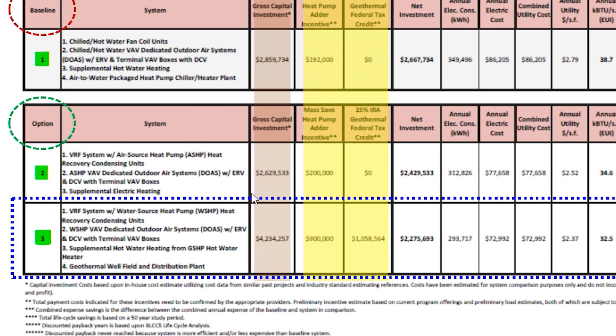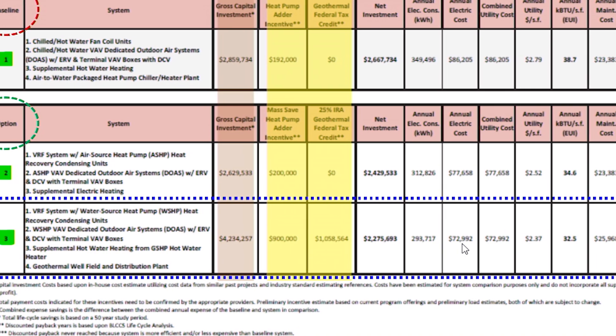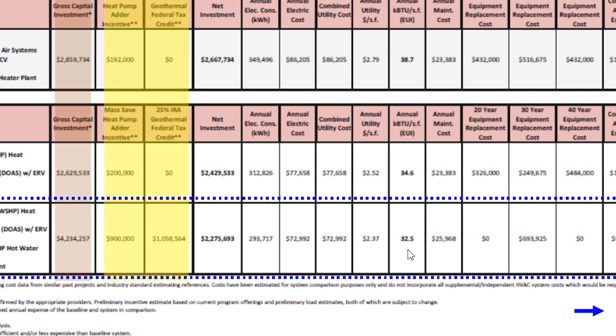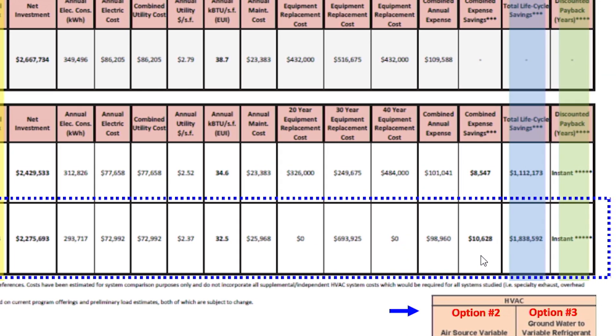The third option — the geothermal — is the one the committee chose. On paper it shows that it's 1.4 million more than the base system; however, you get a significant amount of money through both rebate programs, so your net investment is right around 2.2 million. Energy costs are comparable, electrical costs comparable, and we do save some money in equipment replacement and maintenance. In the long term, lifecycle savings over the base system would be just over 1.8 million — more than option two.